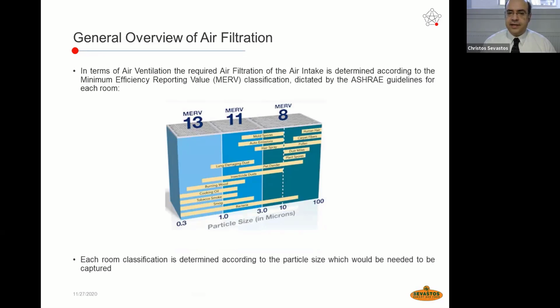As you can see, we have divisions in the scale from 8 to 11 to 13. According to the classification that we need to define in our room, in terms of minimum efficiency reporting value, we have here the particle sizes that we can isolate by air filtration. So if we need to make an air filtration as well, we need to classify our room in terms of minimum efficiency reporting value from 8 to 11 to 13. As we move from 8 to 11 to 13, we manage to absorb and filtrate the air in terms of the minimum possible particle sizes.